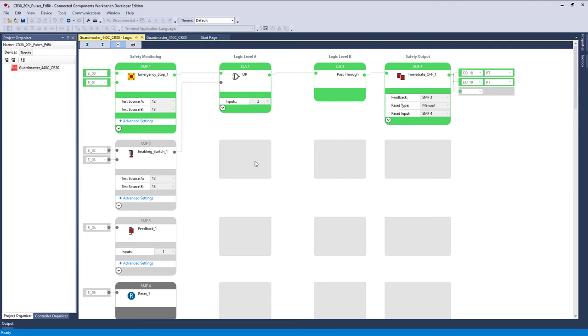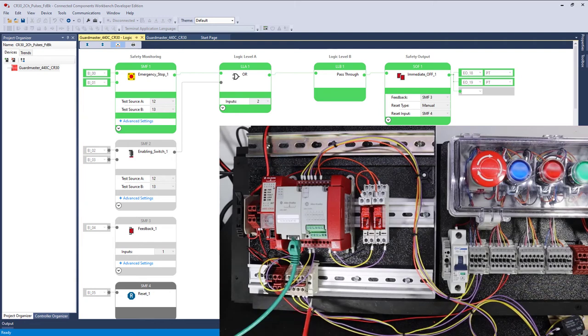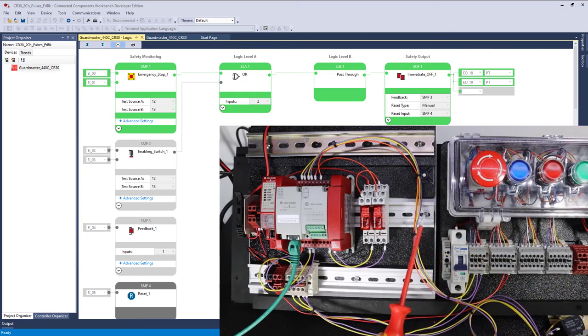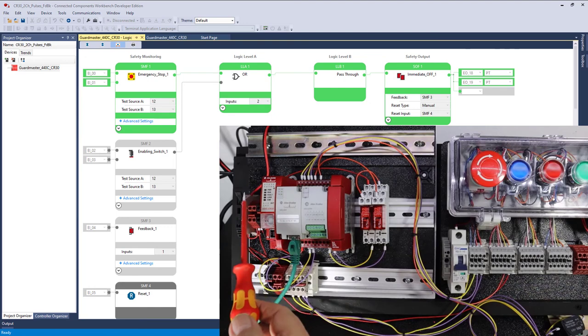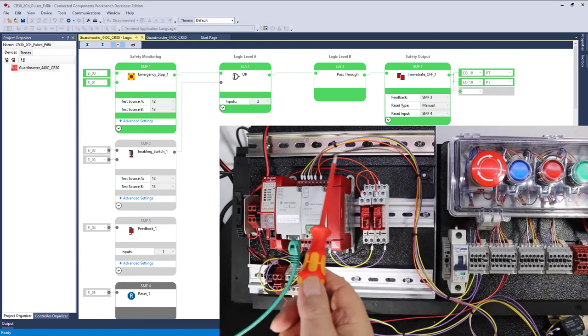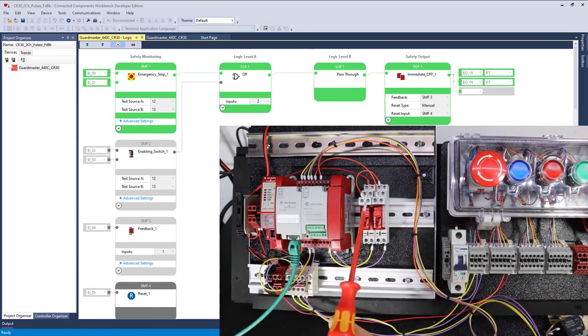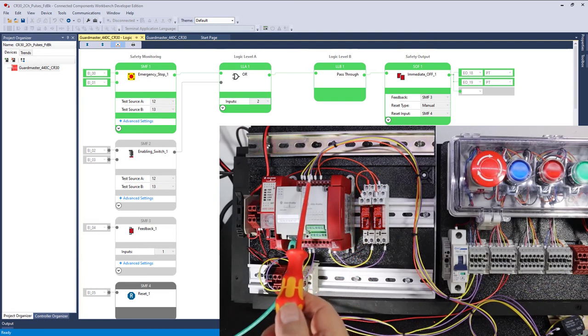Looking at the hardware, a quick reminder. Yellow and purple feeds our enabling switch and our e-stop switch with test pulses. Our feedback is running straight from 24 volts DC through these two relays through normally closed contacts and then into input four.